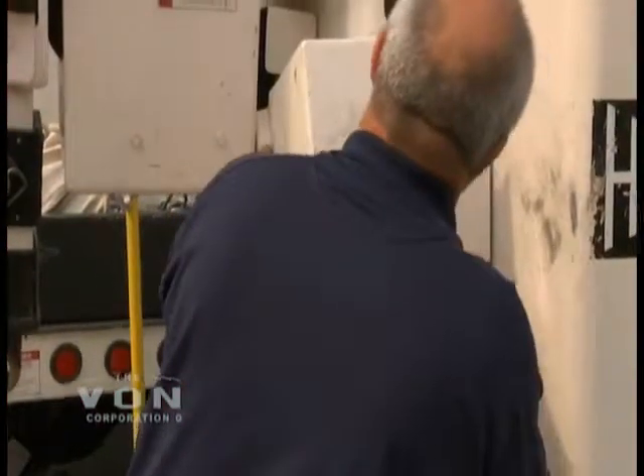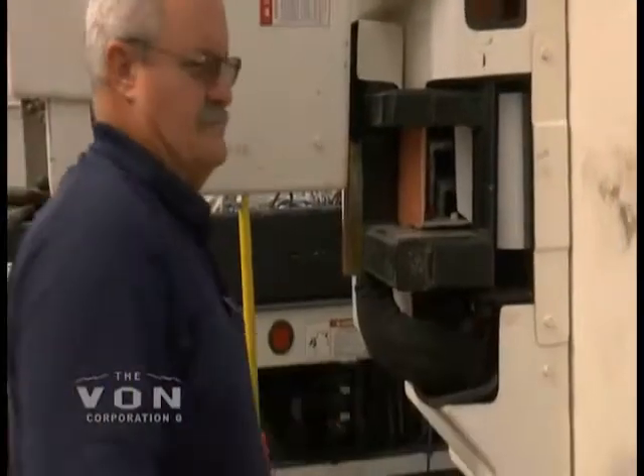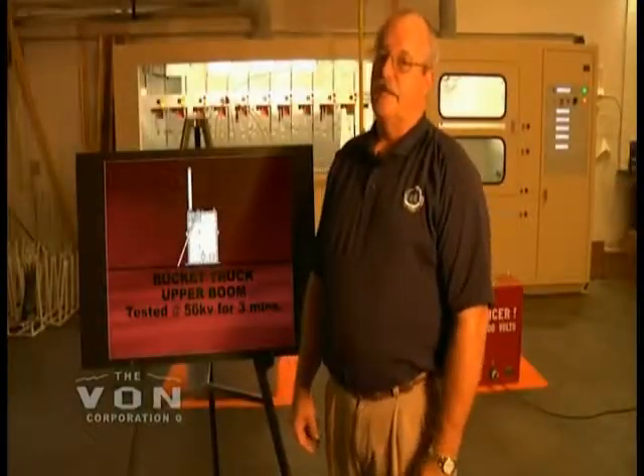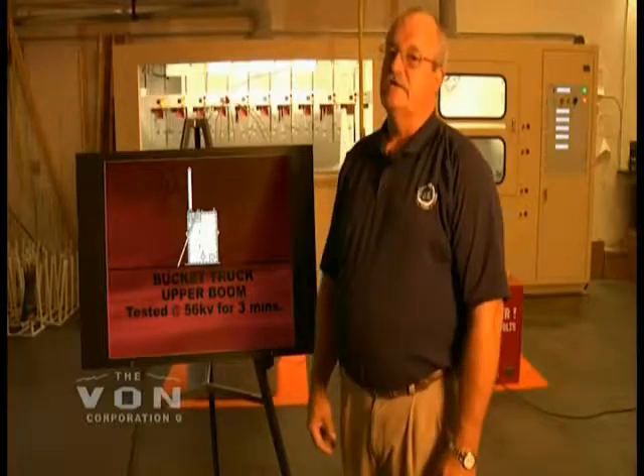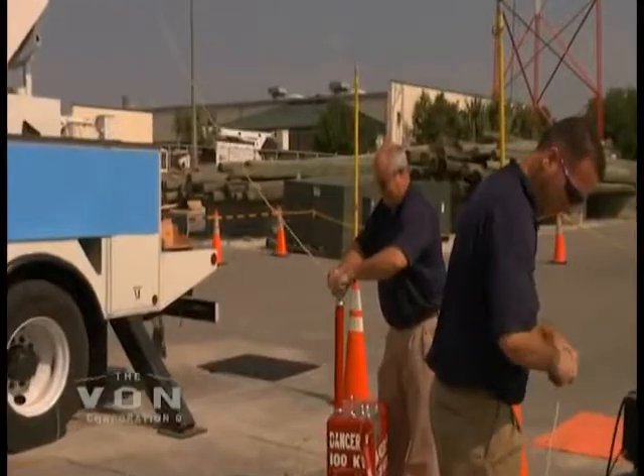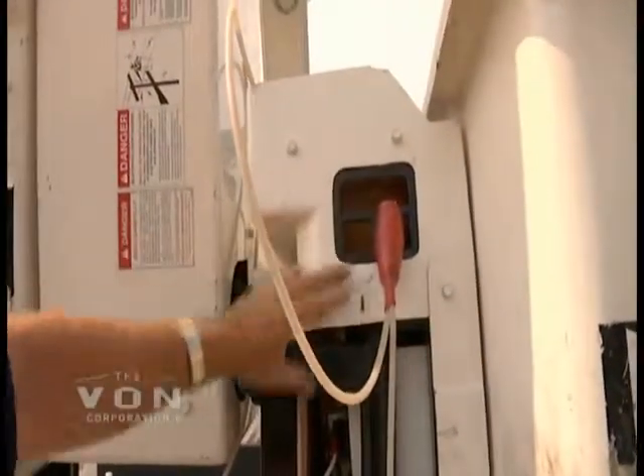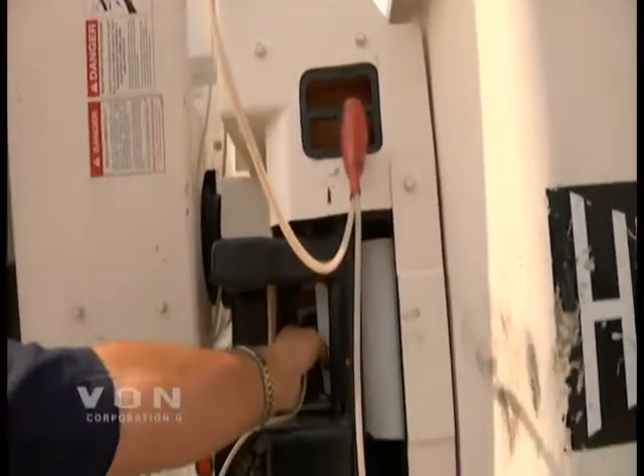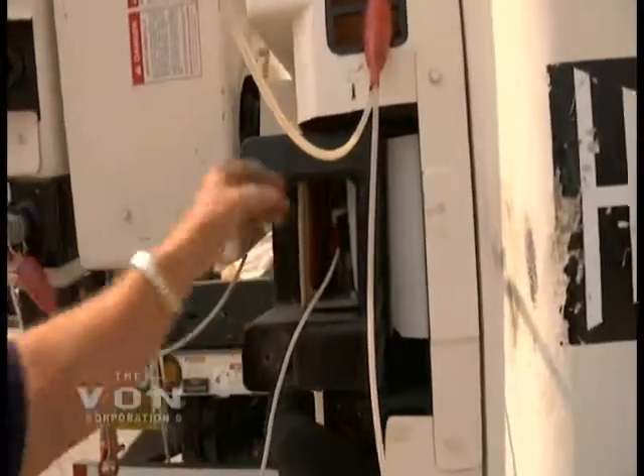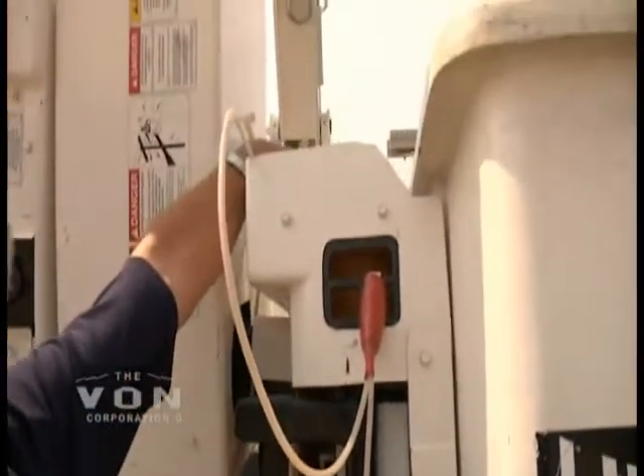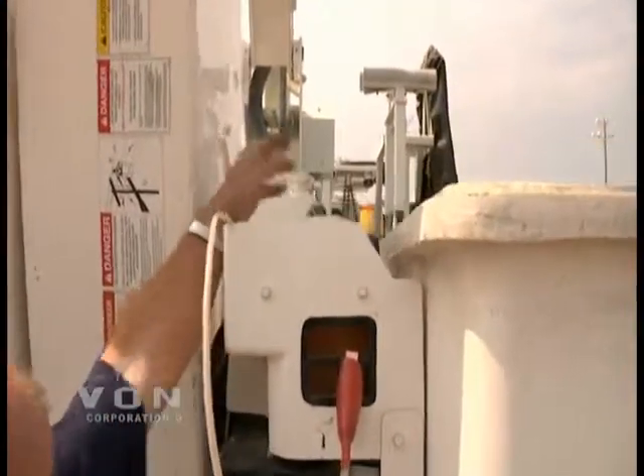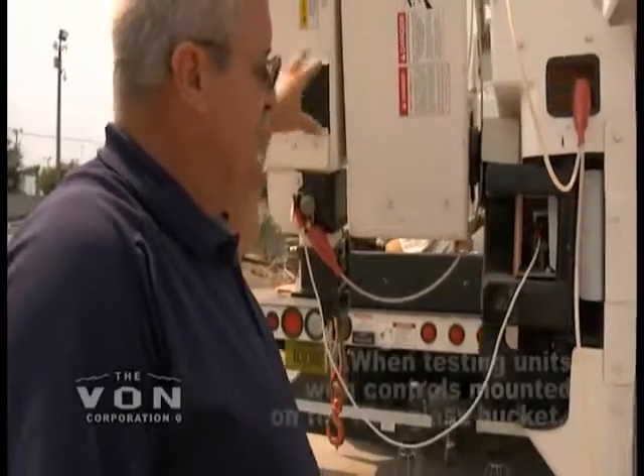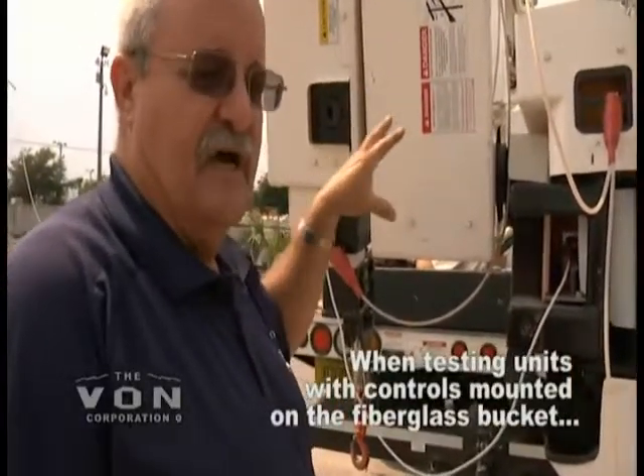We are now going to test the upper boom of this bucket truck. When connecting the upper boom to the high voltage test leads, you need to ensure that you connect all metal components. When we connect the high voltage leads for the upper boom test, we connect to all metal parts at the bucket. We connect to the mounting frame. We connect to the hydraulic lines that feed the controls and the tool circuit. We connect to the control handle. We also connect to the metal where the material handling jib is. This way, the lineman, the customer, is ensured that all metal parts are energized.